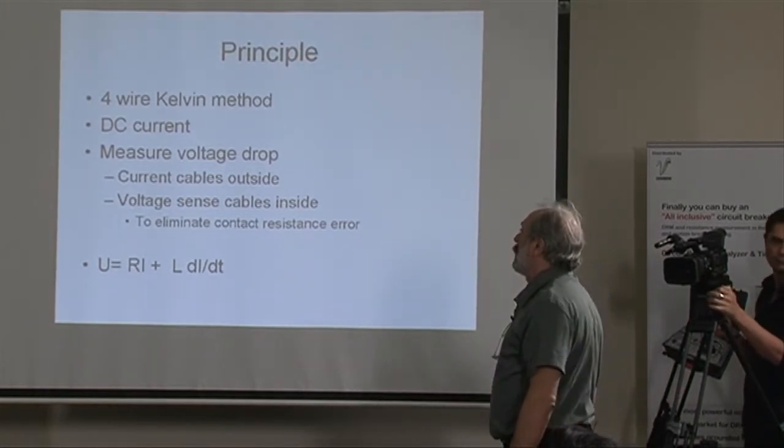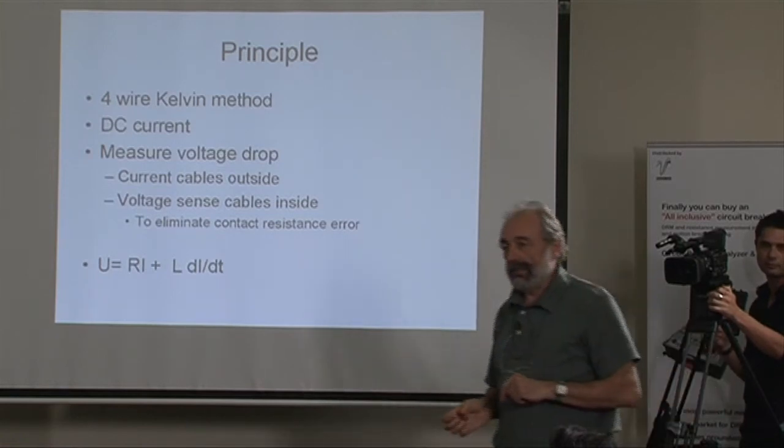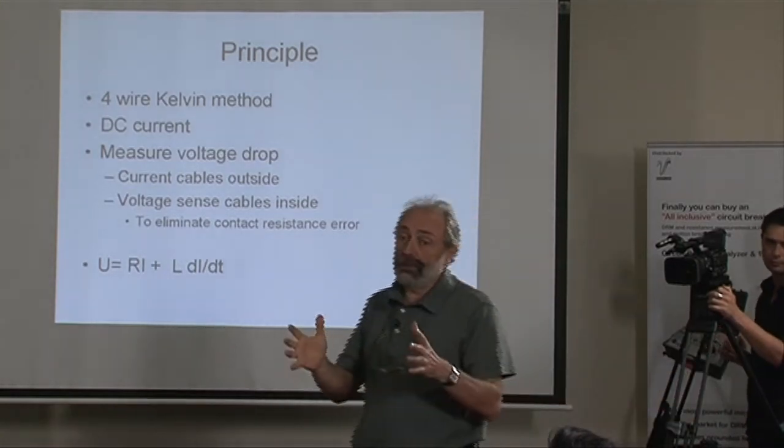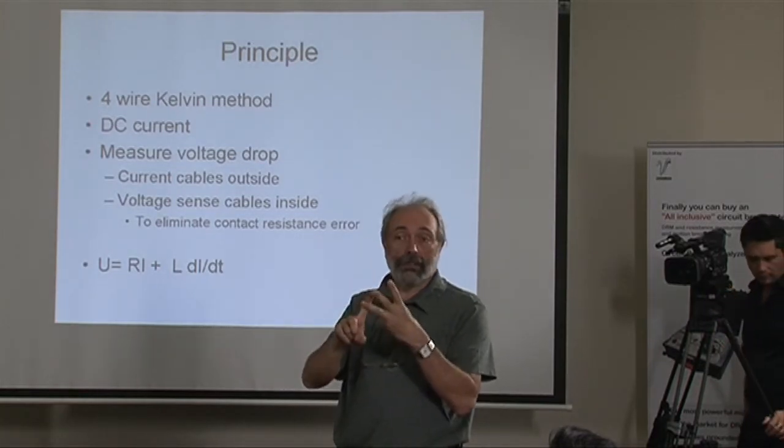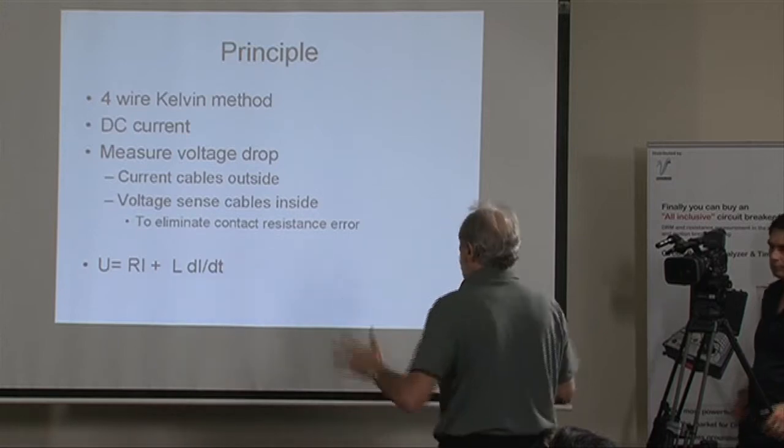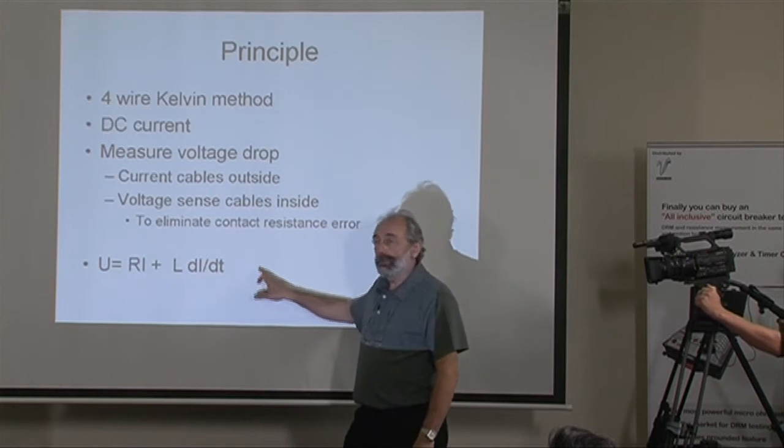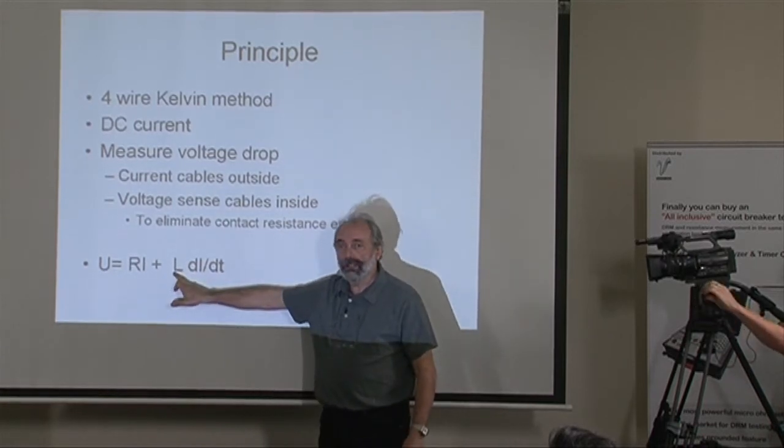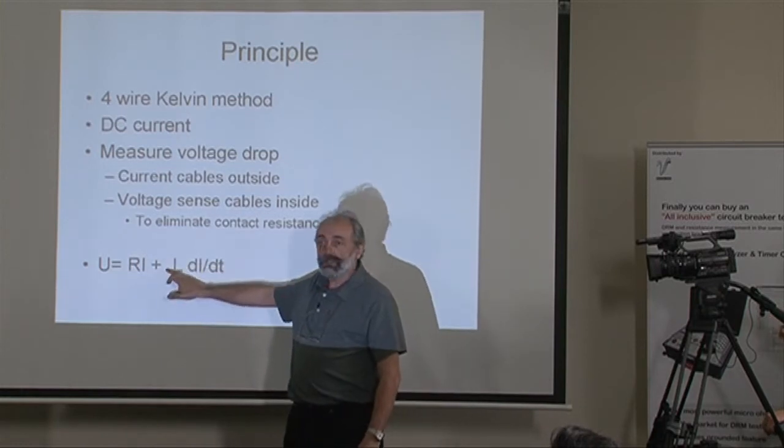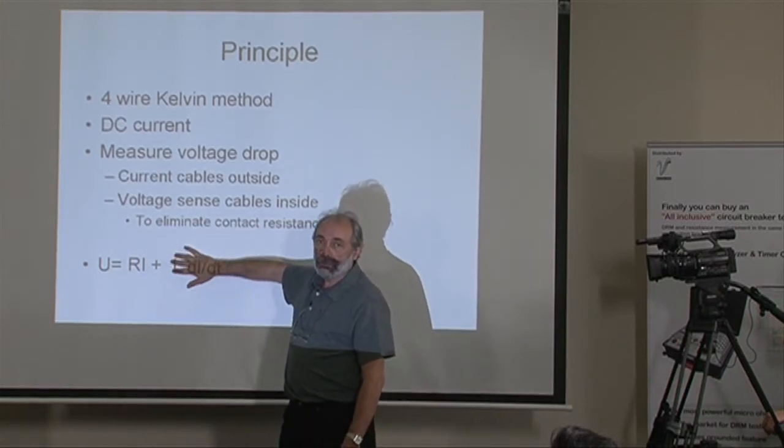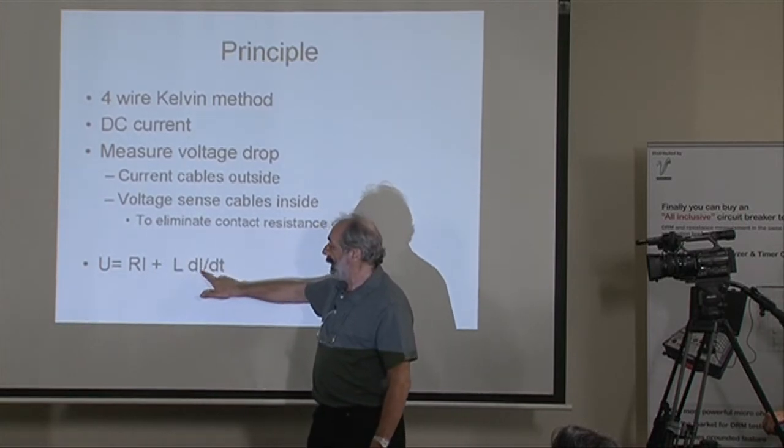Always current cables outside, voltage cables inside. And now what you do is you know the current, you measure the voltage, you calculate the resistance. Right? Wrong. As long as we deal with the transformer that has inductance, we have a component that introduces an error in our measurement and we need to deal with this. This is di dt, or change of current in time.